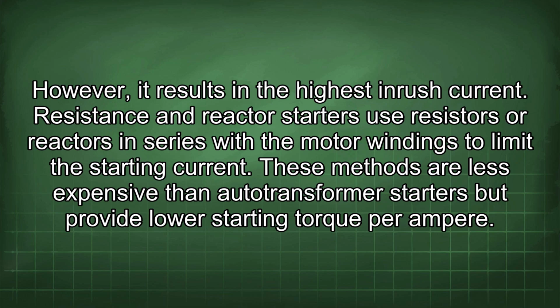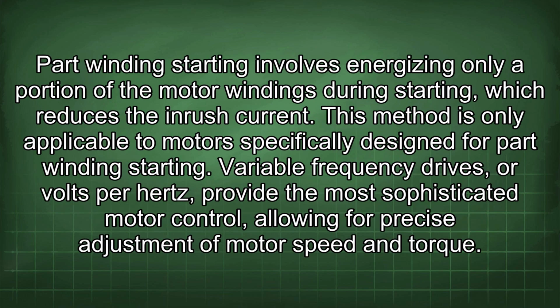Resistance and reactor starters use resistors or reactors in series with the motor windings to limit the starting current. These methods are less expensive than autotransformer starters but provide lower starting torque per ampere. Part winding starting involves energizing only a portion of the motor windings during starting, which reduces the inrush current. This method is only applicable to motors specifically designed for part winding starting.